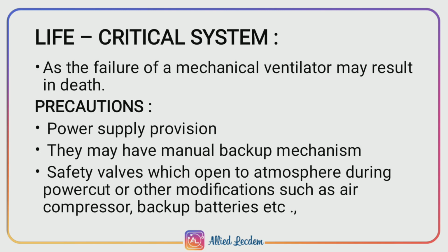Life critical system. As we know, the breathing of a patient is carried out by the mechanical ventilator. A failure of that ventilator can lead to death of the patient. Precautions. While switching to a ventilator, we should always be cautious about the power supply, manual backup mechanism, and safety valves, which will open to the atmosphere during a power cut.